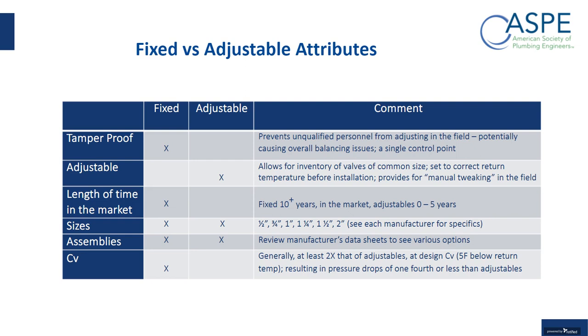Sizes, they both come in multiple sizes. You have to look at each manufacturer and see what sizes are available. Again, probably over 90% of what is being used is 1/2 inch to 3/4 inch. There are applications we're seeing more and more that are 1 inch, and we also come across a lot of applications for dual systems. By dual system, I mean one that does a combination of heat and recirc hot water. Some of those end up being 2 inches.